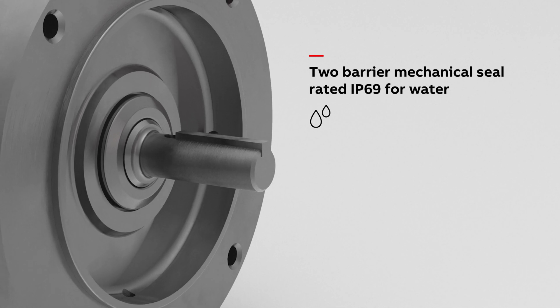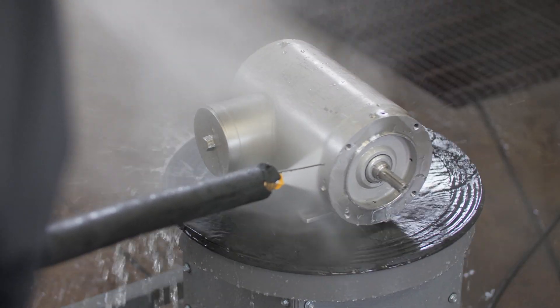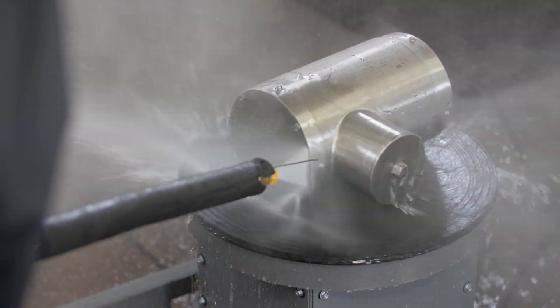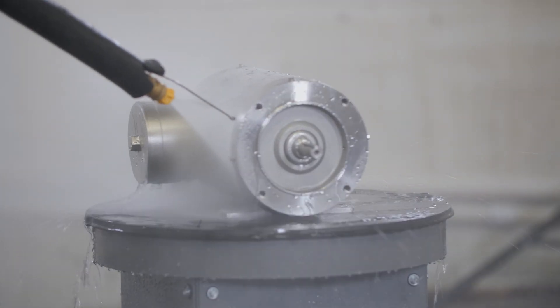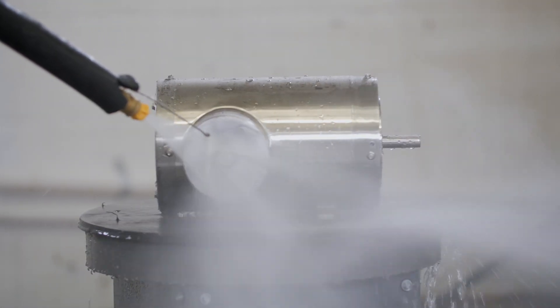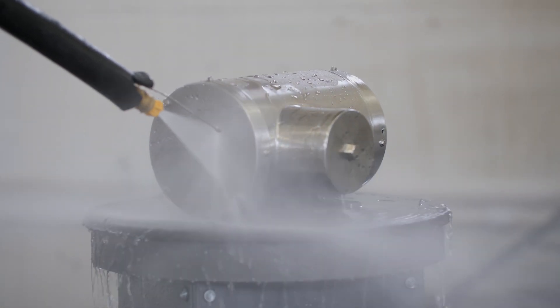FoodSafe motors are tested to the limit, ensuring that the motor can withstand high-temperature, high-pressure spray at close proximities. The test requires water to be sprayed directly on the product at 0, 30, 60, and 90 degree angles, from a distance of 4 to 6 inches away, at 1400 psi and 176 degrees Fahrenheit, while rotating at 5 revolutions per minute.